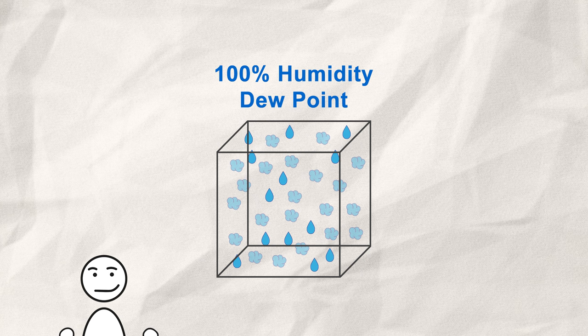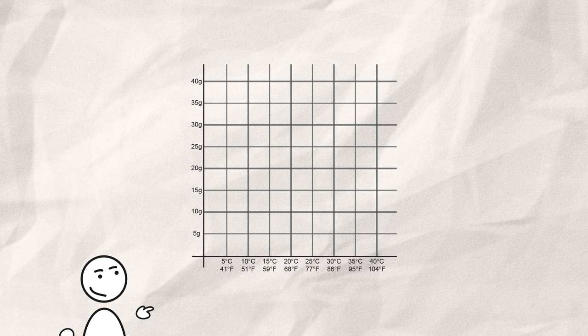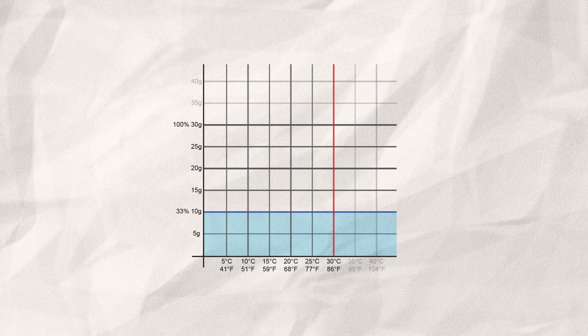But how can we reach such high levels of humidity? Remember, relative humidity is linked to the air temperature. If we take for example air at 30°C with relative humidity of 33% and cool it down to 10°C, the humidity will rise to 100%.